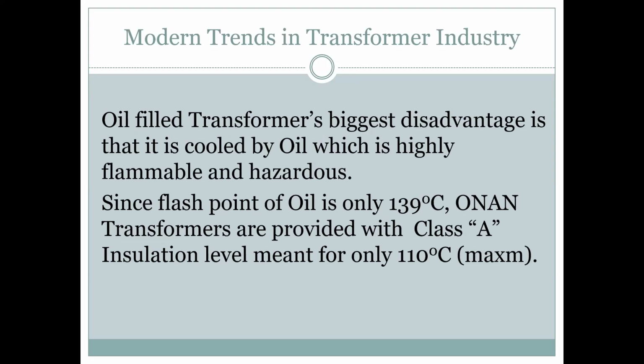Now the oil-filled design's biggest disadvantage is that it is cooled by oil, which is flammable and hazardous. The flash point of oil is 139 degrees and the operating temperature of class A insulation is 110 degrees. So it is hardly a 20, 25, 30 degree difference. So any flash, because of a loose connection or anything, any flash in electrical joints, it will catch fire. So it is very, very dangerous because the oil flash point is close, and your flash creates a 100 degree centigrade temperature, and immediately the transformer can catch fire. So this is the most negative point of an oil-filled transformer. So we have to be very cautious that our operating temperature should not cross 110 degrees class A, or that's why the specification is reduced by 5 degrees, so that we immediately get an alarm and trip and isolate the transformer.